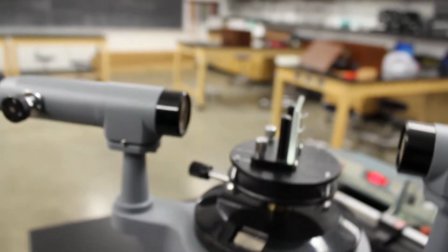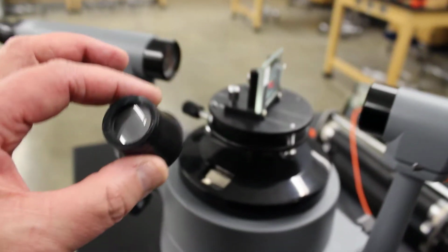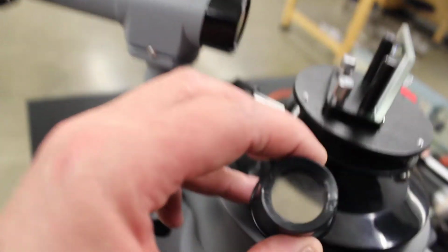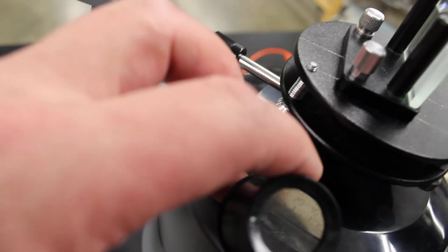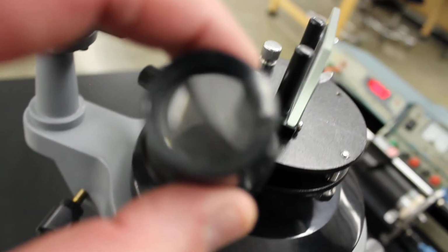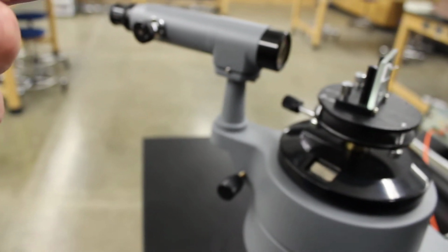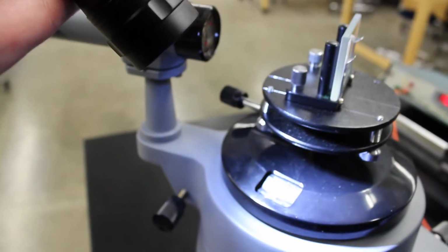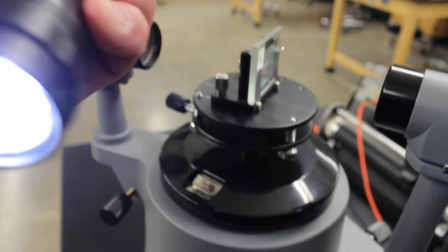The vernier scale is hard to read, so there's two other things we need. This is a magnifying glass, and we can hold that magnifying glass, and you can actually read much better through the magnifying glass. This magnifying glass comes with the spectrometer, and I also have a flashlight that helps a lot in illuminating. So you illuminate that and you make the reading. So that's about it.